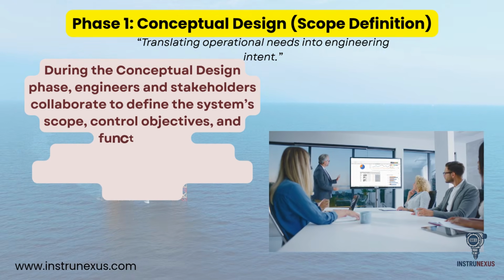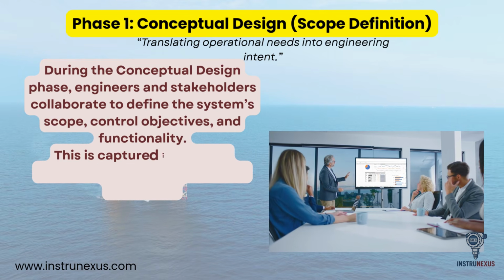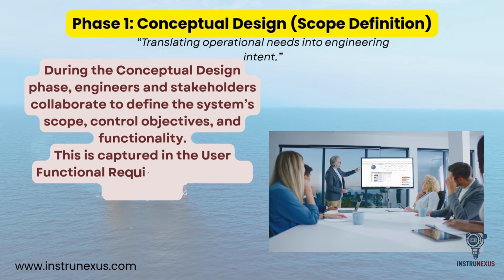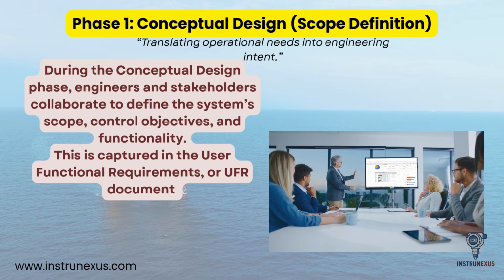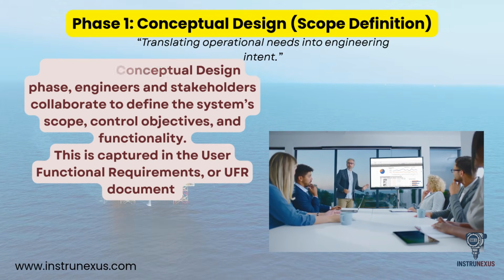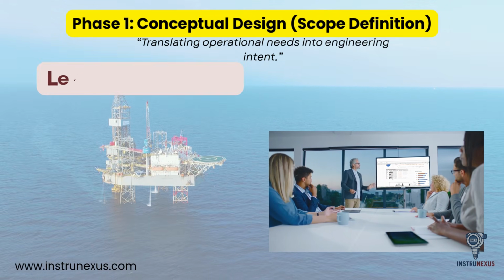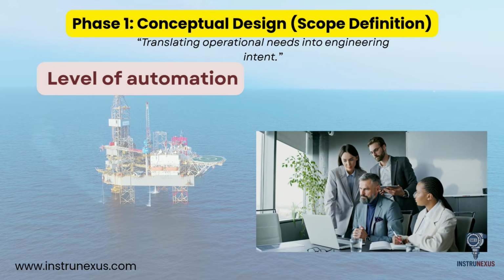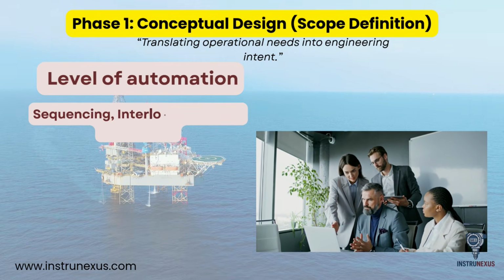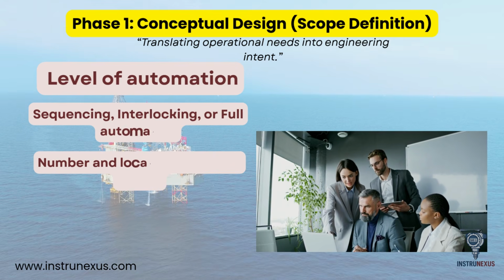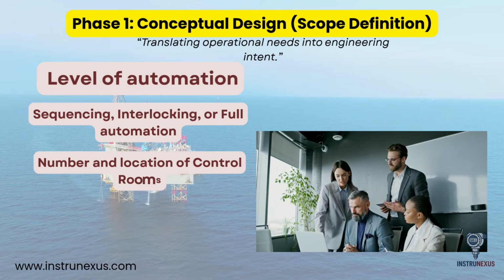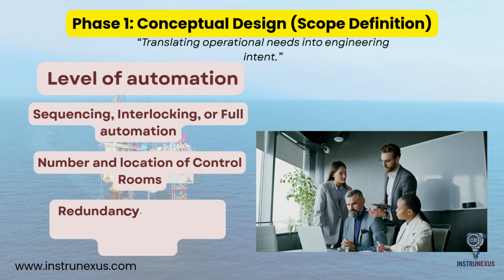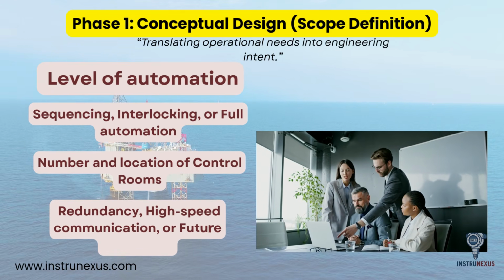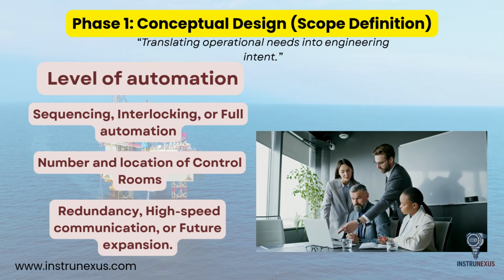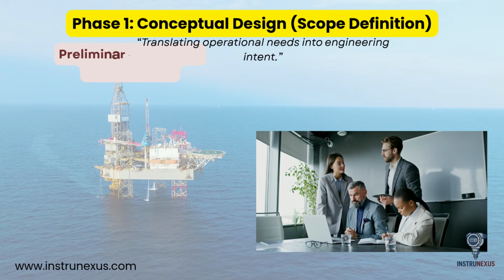This is captured in the User Functional Requirements, or UFR document, the cornerstone that specifies what the control system must achieve. It includes details such as the level of automation, whether the system uses sequencing, interlocking, or full automation, the number and location of control rooms, and any special requirements like redundancy, high-speed communication, or future expansion. The next step is preliminary sizing and configuration.